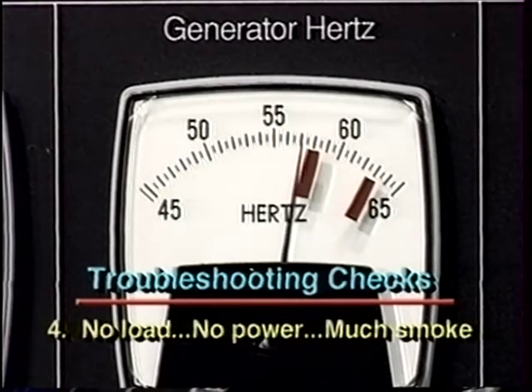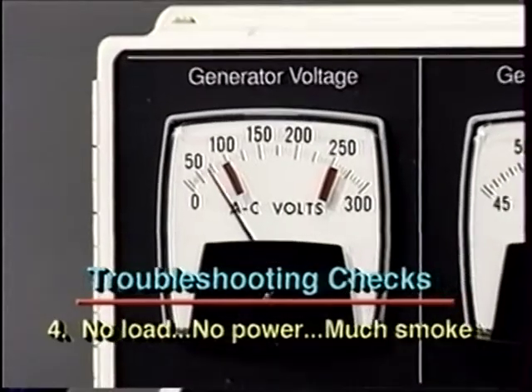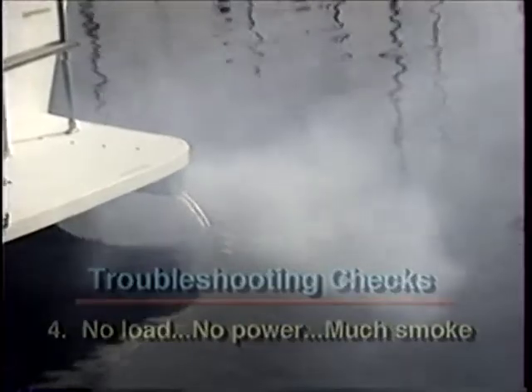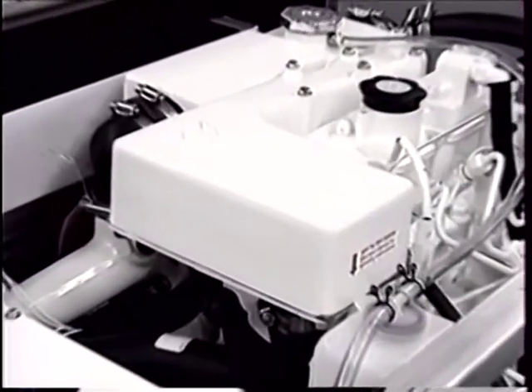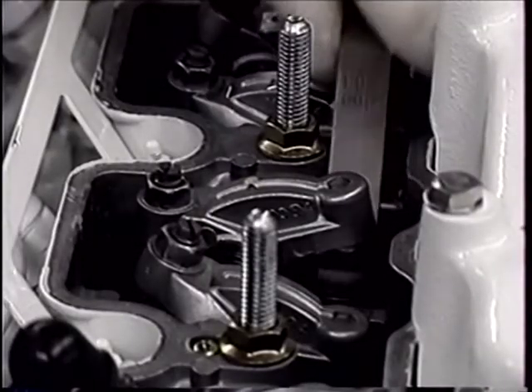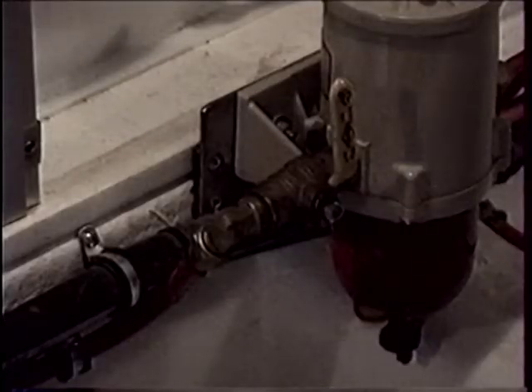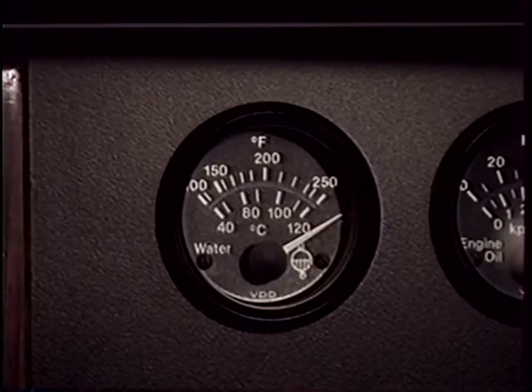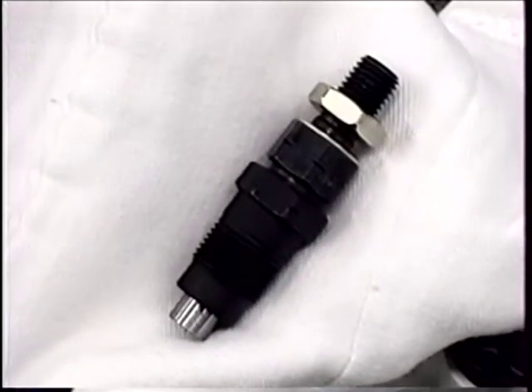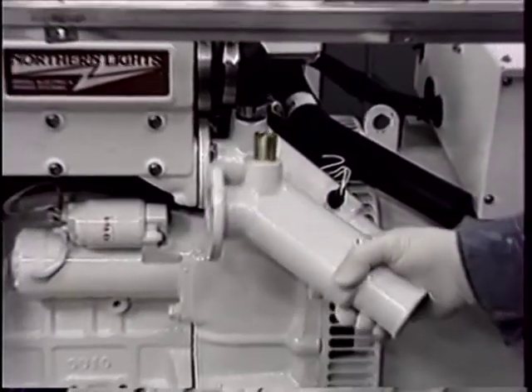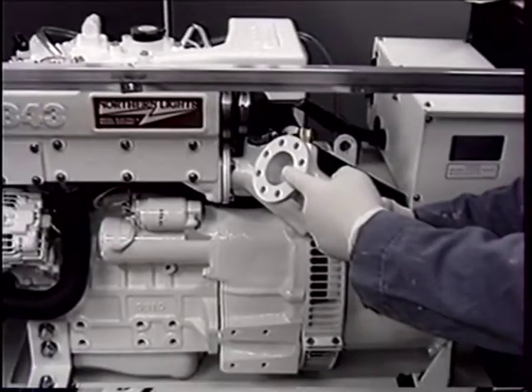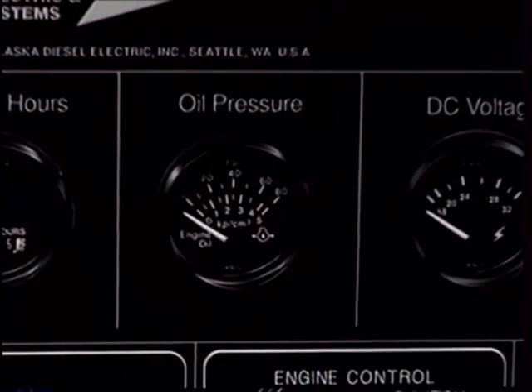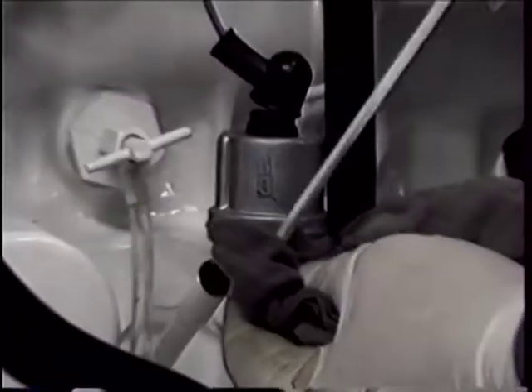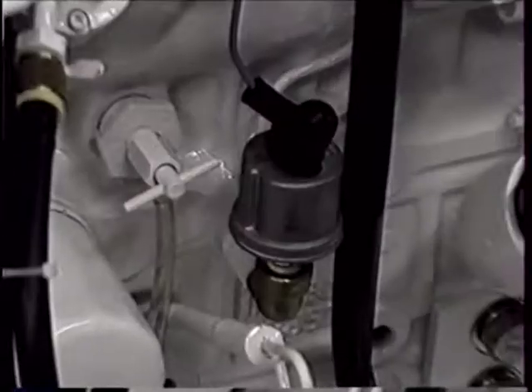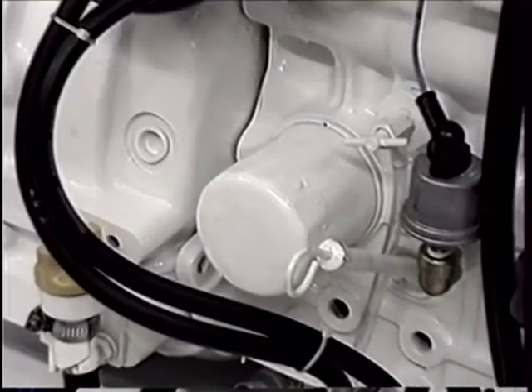If your generator set doesn't seem to carry load well, lacks power, or has excessive smoke, the causes can be a plugged air filter, valves out of adjustment, a restricted fuel system, an overheating engine, an overloaded engine, dirty or faulty fuel injectors, or a plugged exhaust elbow. Other abnormal engine problems can be a fluctuating oil pressure gauge, low engine oil level, a bad sender, wiring, or a plugged oil filter.